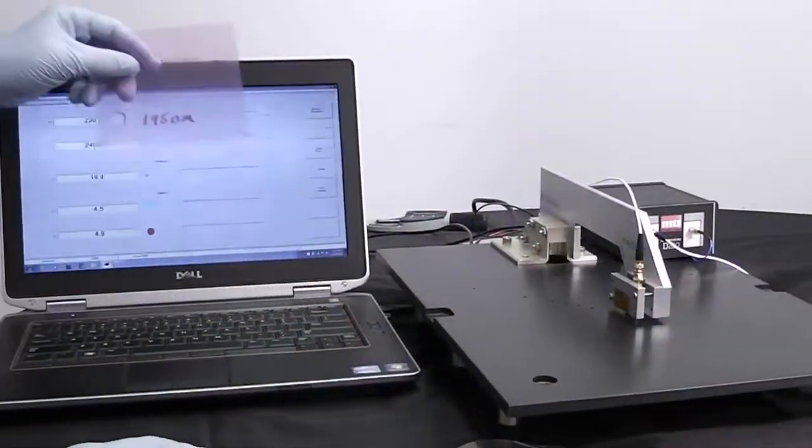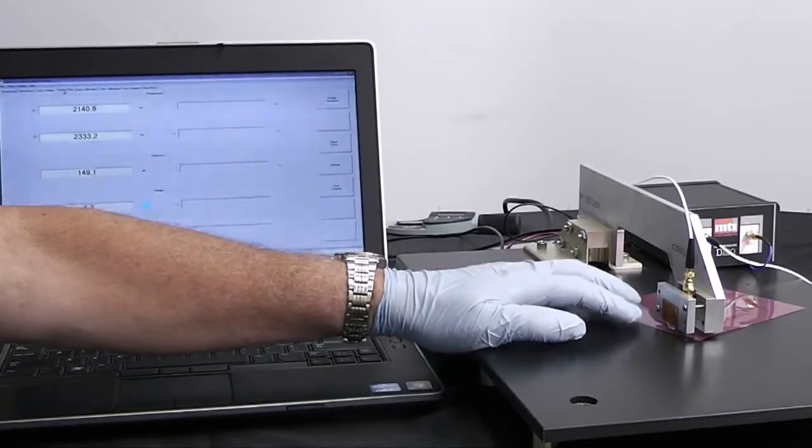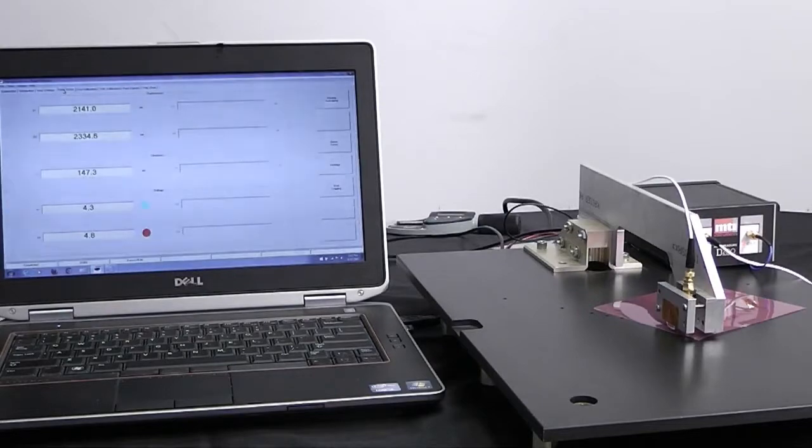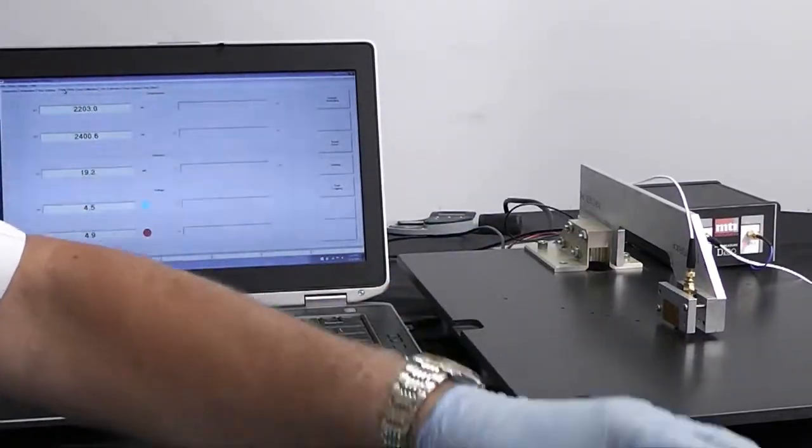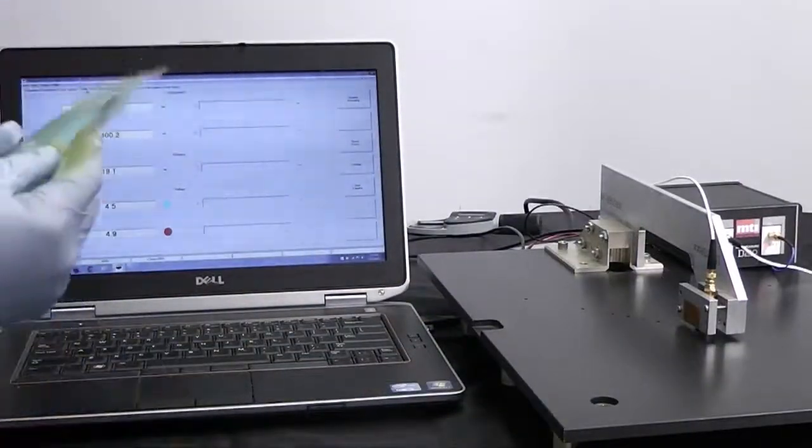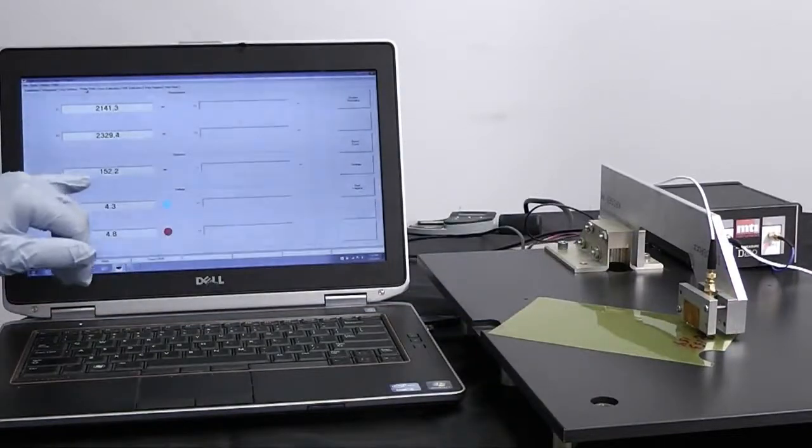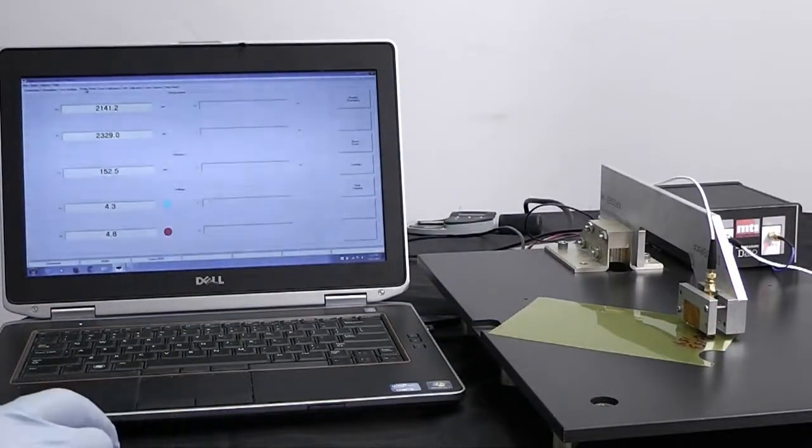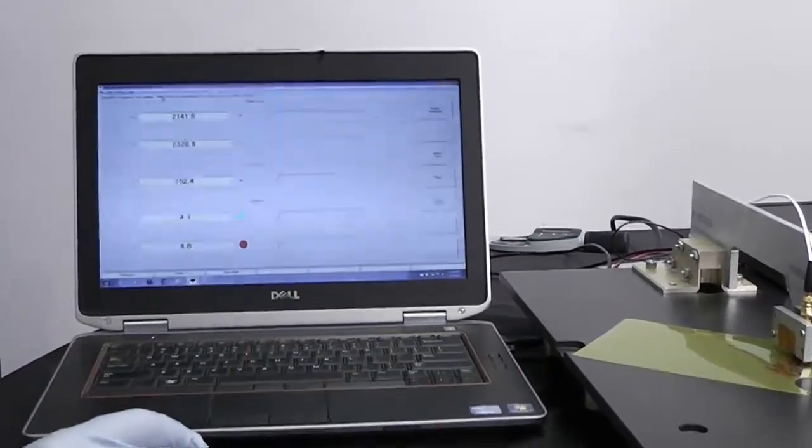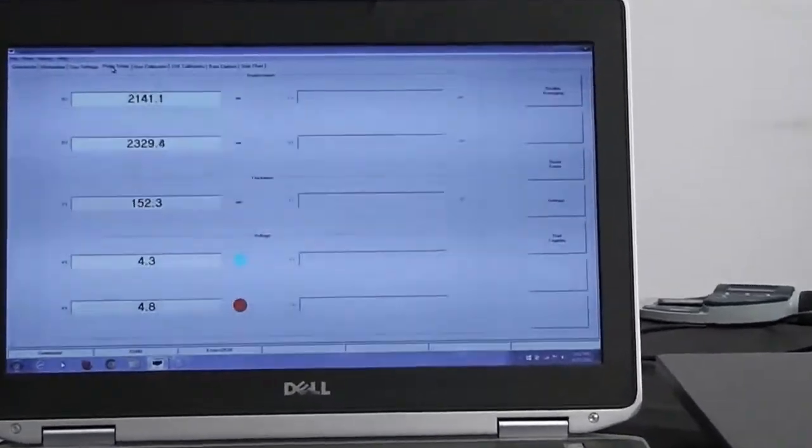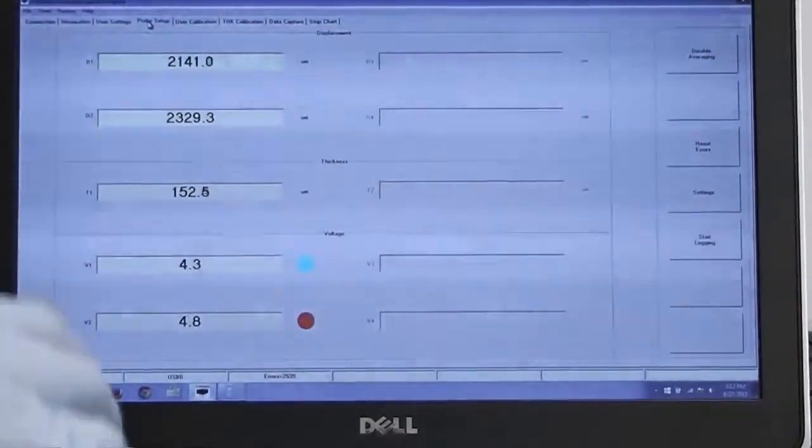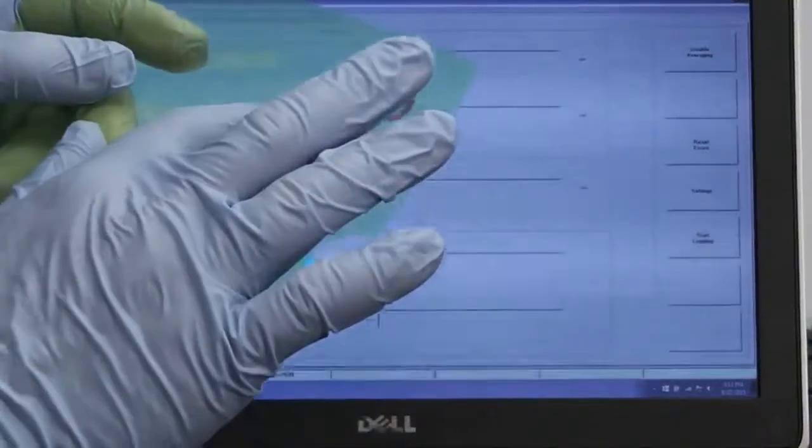So, I have another sample here. This is 145 microns. We'll slide that under. This is reading 147, so it's within 2 microns. We have another sample here. This one is 153 microns. And we're reading 152. So with plastic samples like this, the accuracy within 1 to 2 microns is considered pretty good. We can get higher accuracy if the samples have higher accuracy themselves. And it's a function of cleanliness, the waviness on the plastic samples, and on these there's also little divots and dings and things that have been used from shipment and handling.